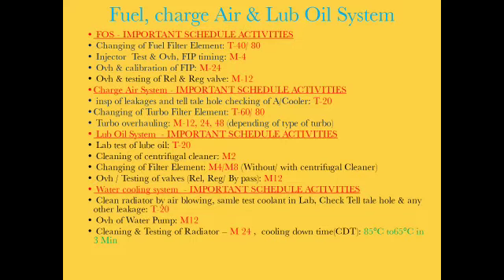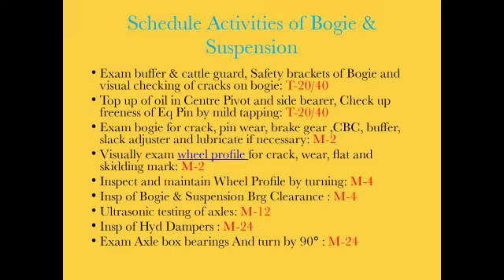Water cooling system, important schedule activities: clean radiator by air blowing. Sample test coolant in lab. Check telltale hole and any other leakage T20. OVH of water pump M12. Cleaning and testing of radiator M24. Cooling down time CDT 85 degrees centigrade to 65 degrees centigrade in 3 minutes.